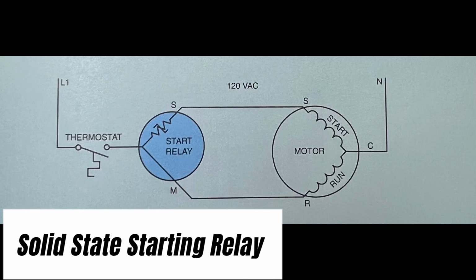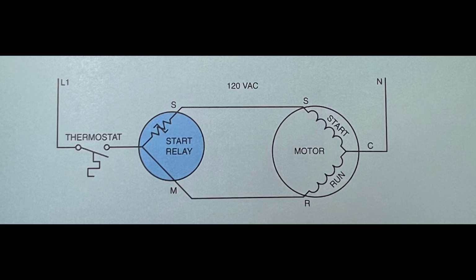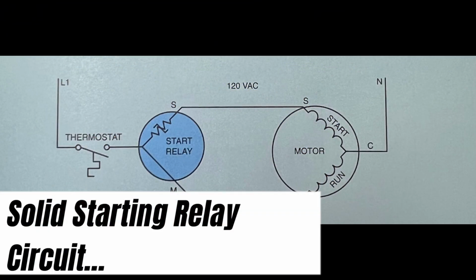Solid state relay starting. The solid state relay starting is rapidly replacing the current starting relay. The solid state relay uses a solid state component called a thermistor, and therefore has no moving parts or contacts to wear or burn. A thermistor exhibits a rapid change of resistance when the temperature reaches a certain point. This particular thermistor has a positive coefficient of resistance, which means that it increases its resistance with an increase of temperature. The next image illustrates the connection for a solid state relay.